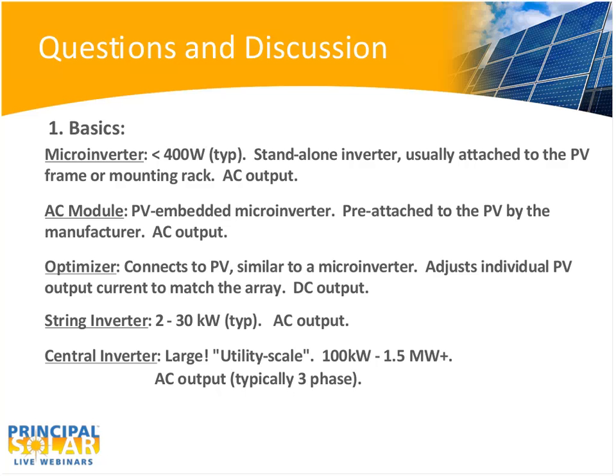There's another concept also in optimizers where they're actually stepping up the voltage from the PV level to some high voltage, say 300 to 400 volts, which reduces the current and subsequently reduces the size of the wire required and consequently the losses involved. It again is DC output only.